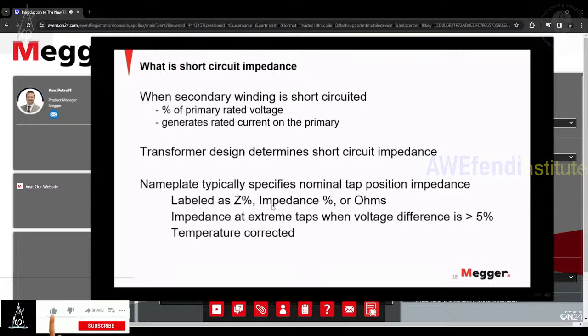One important fact to note here is that the percent impedance will be temperature dependent. On smaller dry type transformers, this may become more important. I would say the larger the transformer, the less impact temperature correction has, because the resistive component of that impedance measurement is a lot smaller in comparison to the other values.